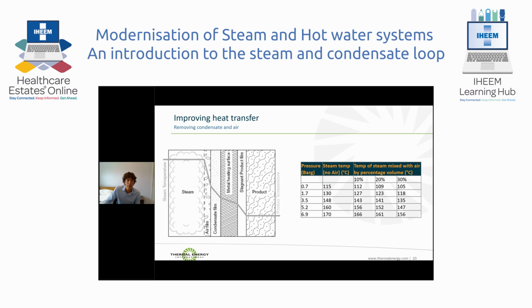How much this affects the overall temperature in the product is determined by the thickness of those walls or heat transfer barriers. Air not only inhibits heat transfer, it also reduces steam temperature due to partial pressures. What this means is when we mix two gases together, in this case steam and air, the pressure that we read on the pressure gauge is partially contributed by the steam and partially contributed by the air. So we might read 2 bar on the pressure gauge, but we've only got 1.7 bar of actual steam, which has an effect, because the steam pressure is related to its temperature, on the temperature that we actually receive. This is particularly important in SSD, the sterile services department, where we rely on achieving temperatures to have full sterilization. So removing air from these systems is particularly important.